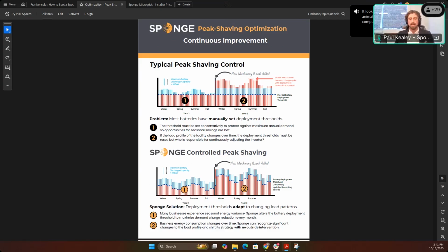But that means that if there's any kind of seasonality in the consumption rate, say this is a business that relies on heating and cooling, there are going to be times where, due to the set threshold, you're actually not utilizing the battery's full capacity. You can look towards that spring area at the top of the screen. So that's unfortunate, you're not maximizing your savings in that case.